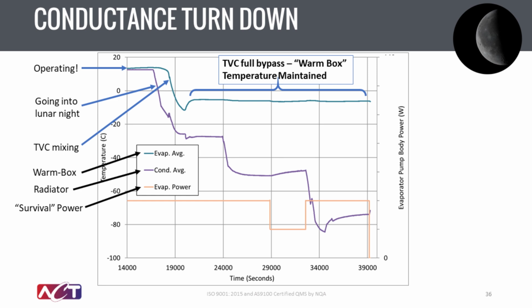As that temperature got down to about negative 10 degrees C, we can see that the thermal control valve then goes into full bypass mode, and the evaporator temperature is maintained a little bit above negative 10 degrees C, regardless of what the radiator, that condenser average temperature, is doing. So it was stepping down from about minus 25 down to minus 50, and then later down to minus 80 without impacting that evaporator average temperature.